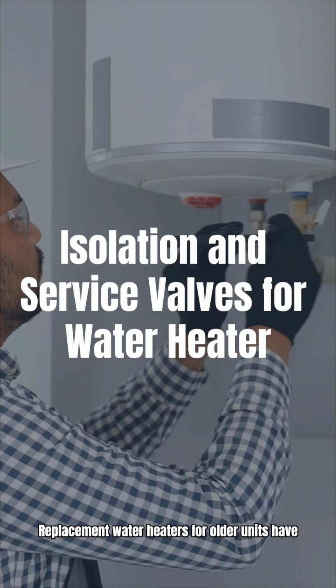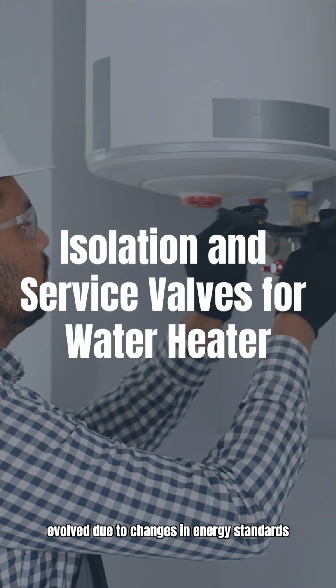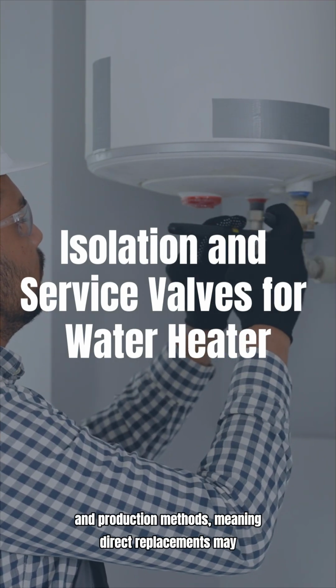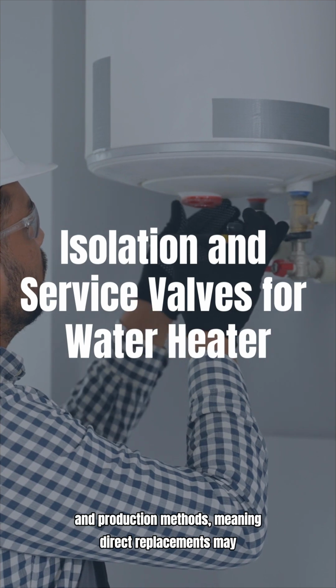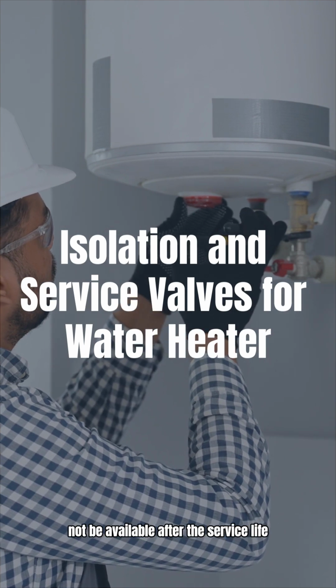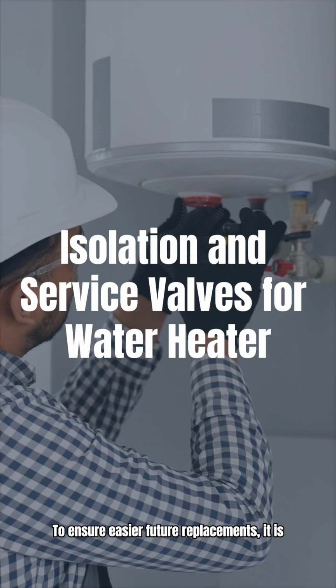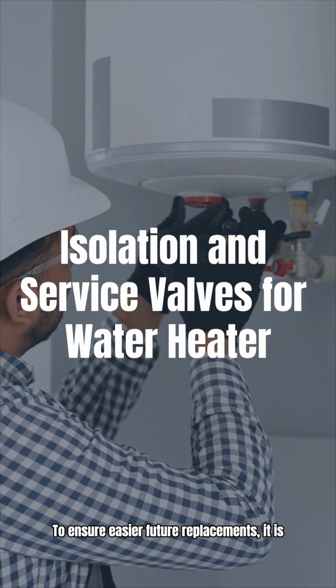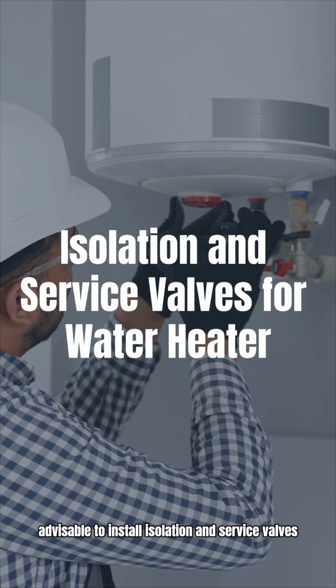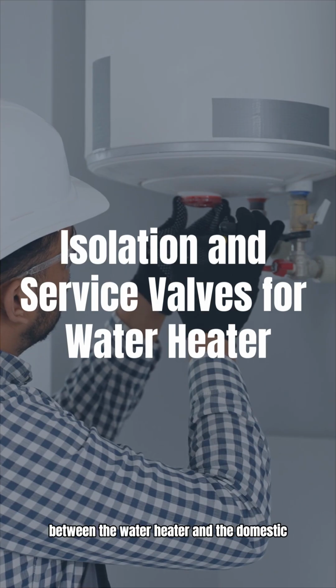Replacement water heaters for older units have evolved due to changes in energy standards and production methods, meaning direct replacements may not be available after the service life of current models. To ensure easier future replacements, it is advisable to install isolation and service valves between the water heater and the domestic water system.